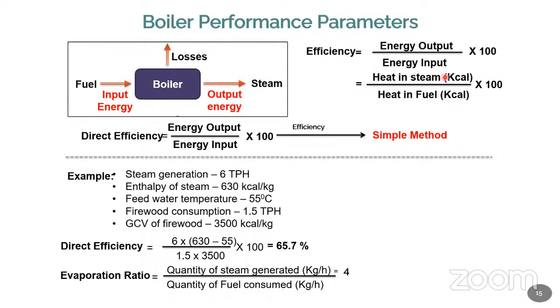Steam content in kilocalories can be taken from the steam table. So at what pressure and at what temperature you are producing the steam, based on that, the energy content of the steam will be taken from the steam table. And the fuel energy content, I already showed you in the previous slide. Wood has its own energy content. Furnace oil, coal, or whatever it may be has its own values. So based on that, you can calculate the efficiency.